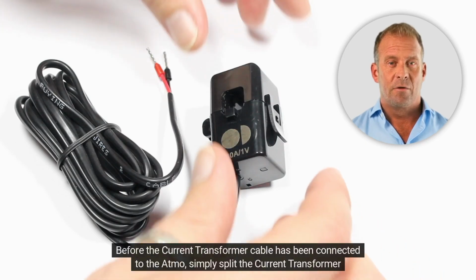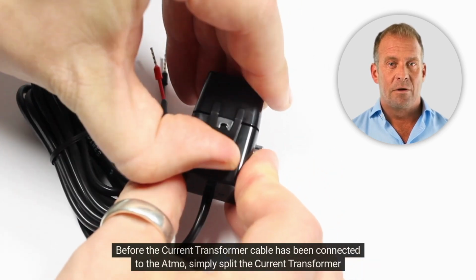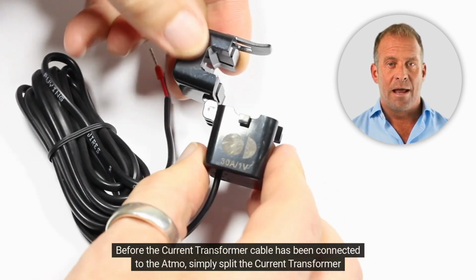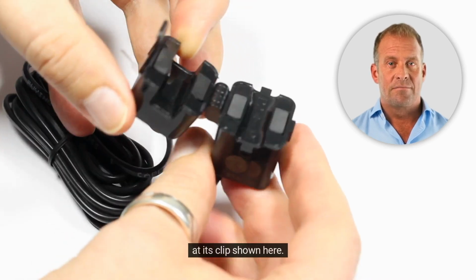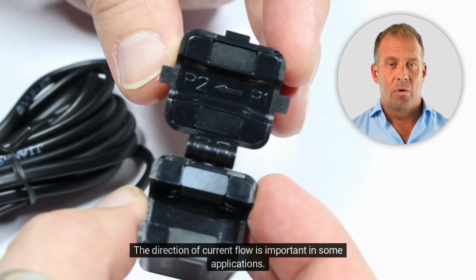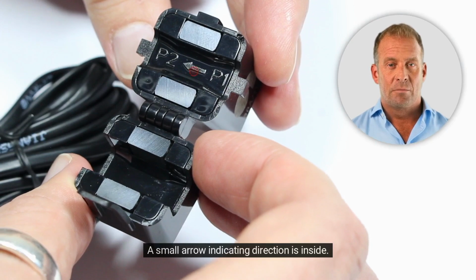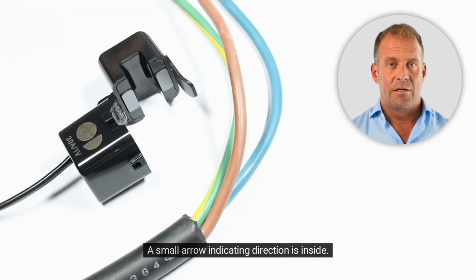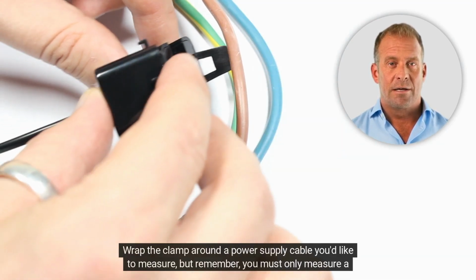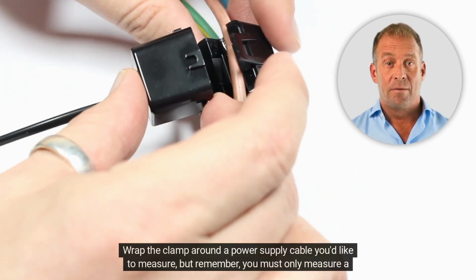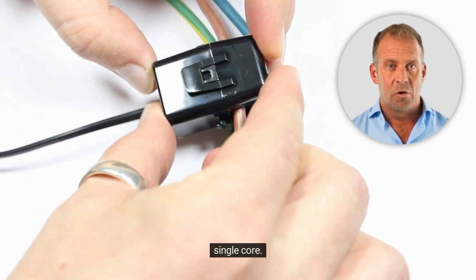Before the current transformer cable has been connected to the Atmo, simply split the current transformer at its clip, shown here. The direction of current flow is important in some applications. A small arrow indicating direction is inside. Wrap the clamp around a power supply cable you'd like to measure, but remember, you must only measure a single core.